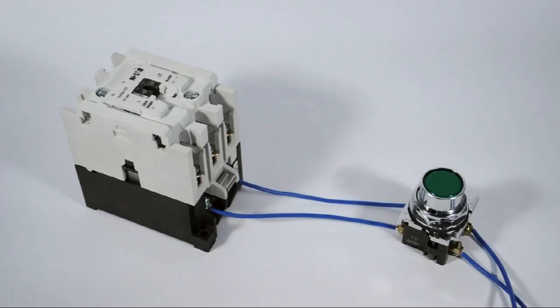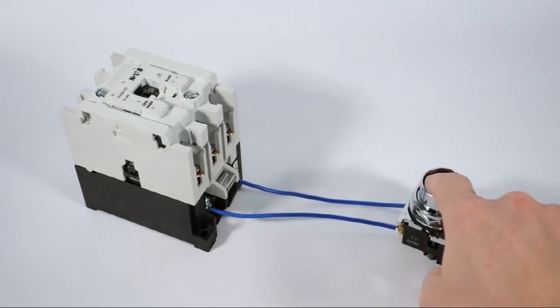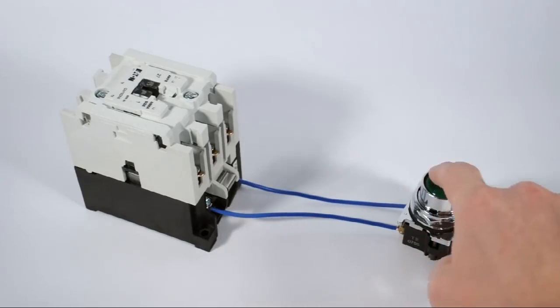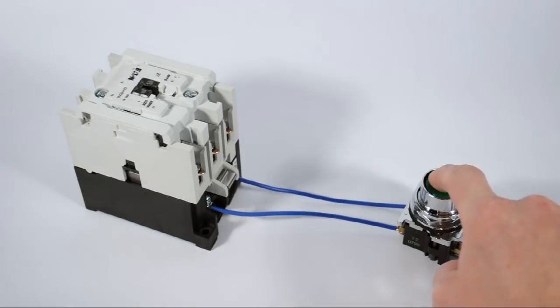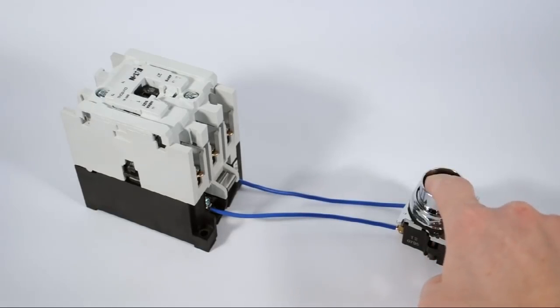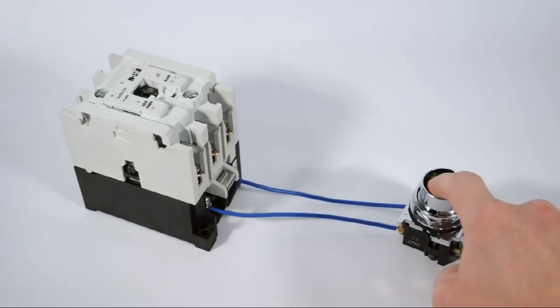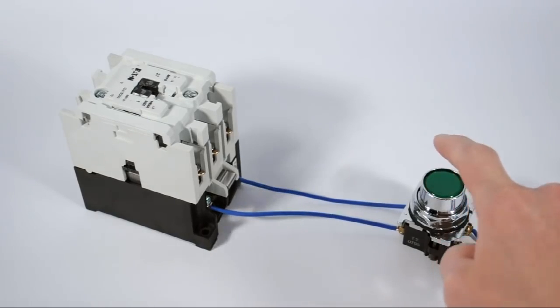What I've done here is I've connected a green start button to control power and connected the other side of the push button to the coil inside of one of Eaton's Freedom Series contactors. When I push the start button, you can see the small black rectangle on top of the contactor move up and down. That is the top of the armature showing through, which is moving inside the contactor. You can also hear the contacts inside opening and closing, as well as the hum of electricity flowing through the contactor coil.